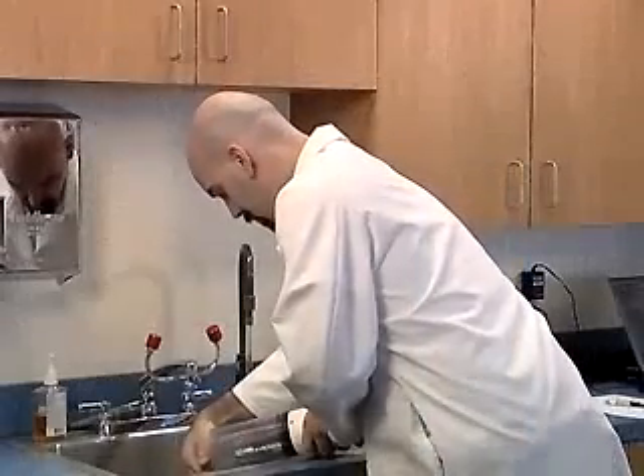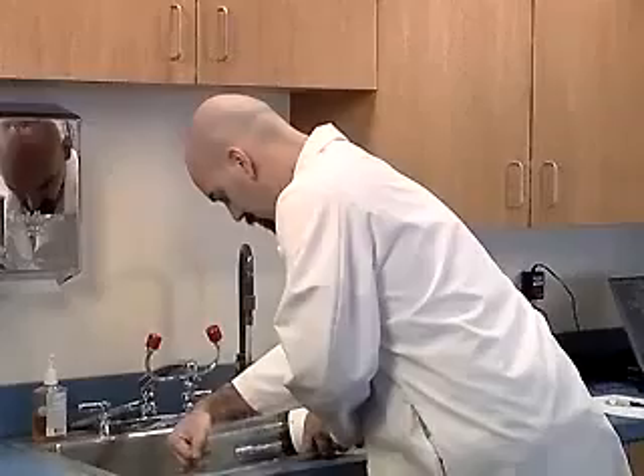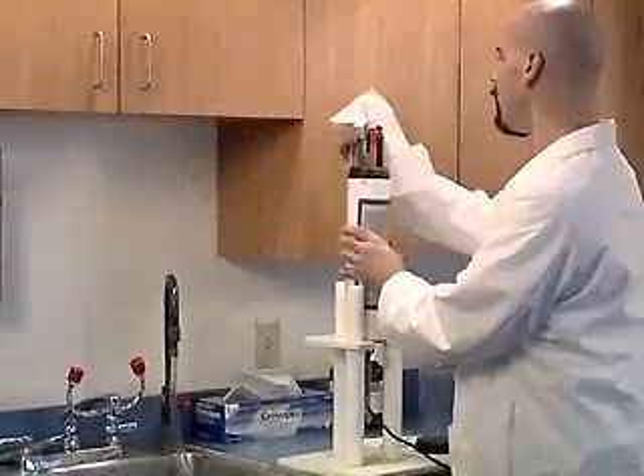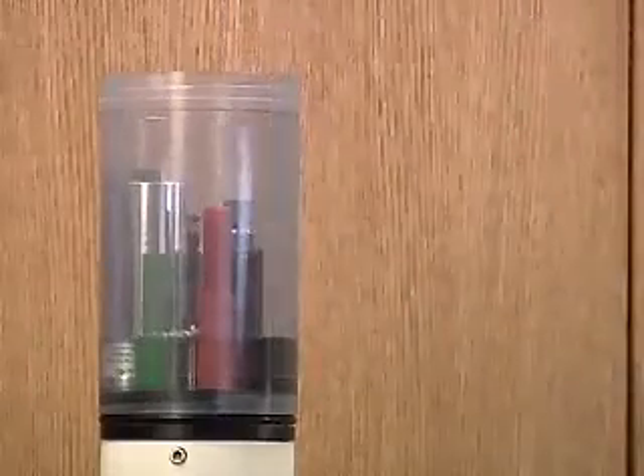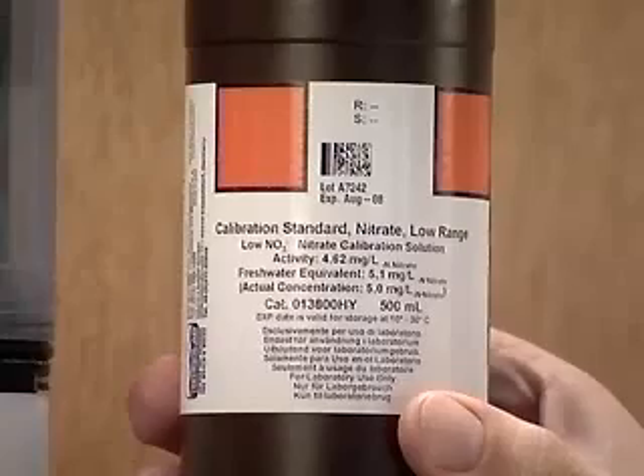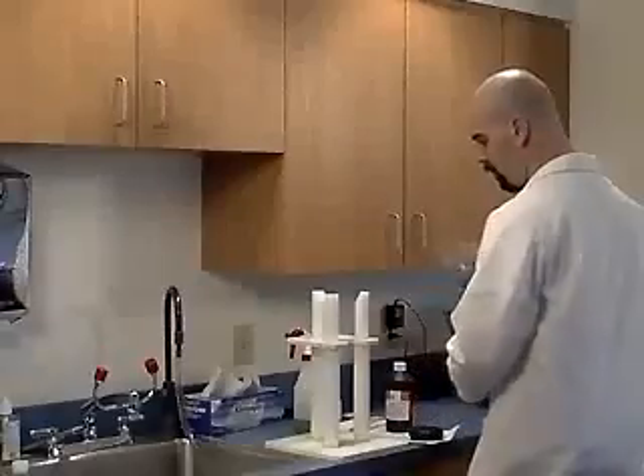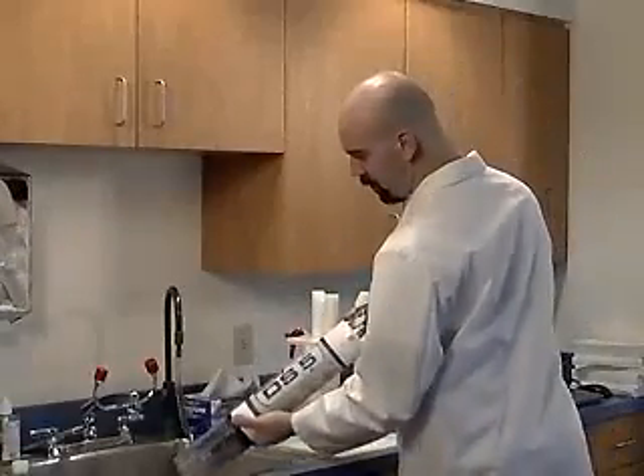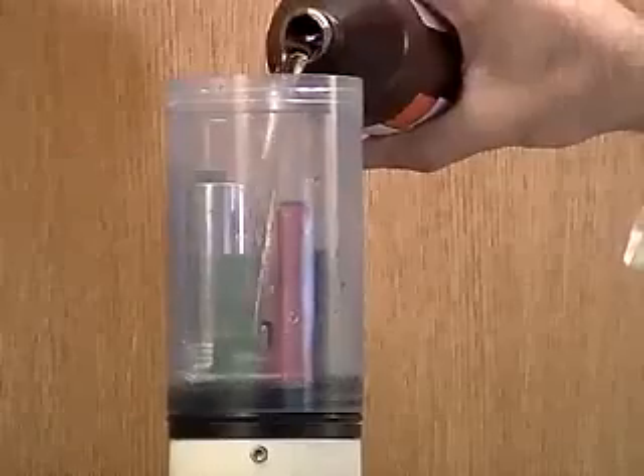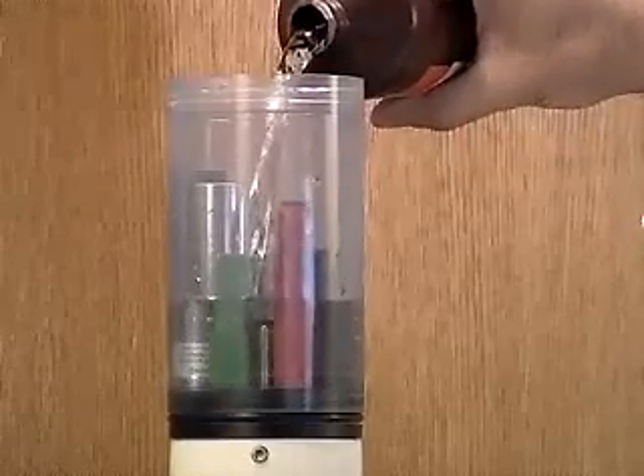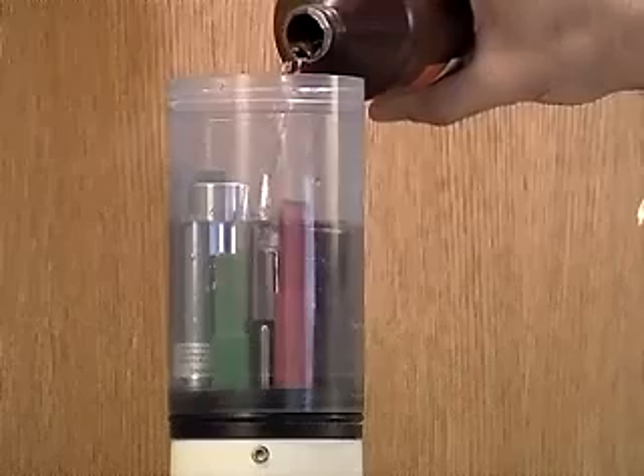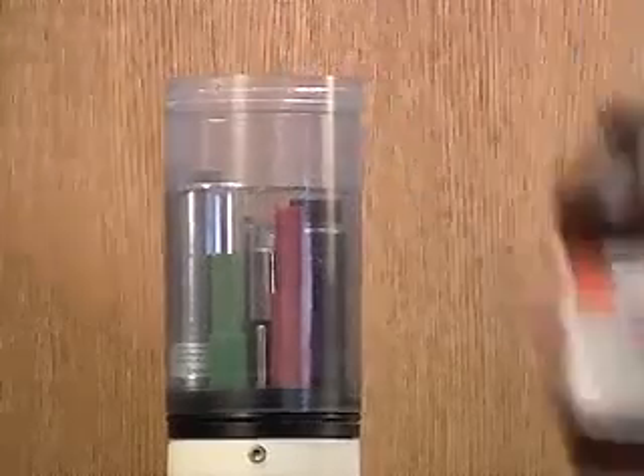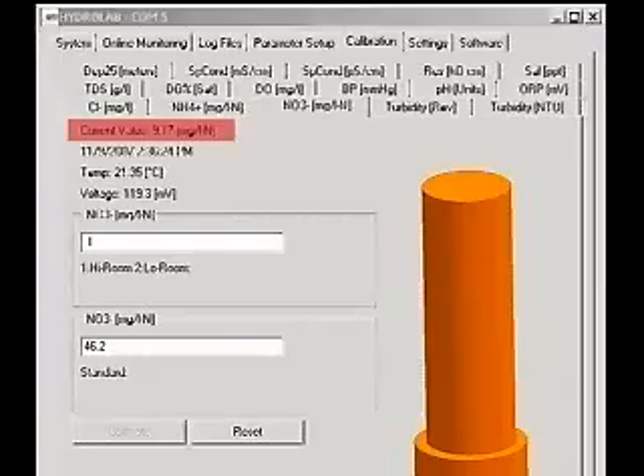Rinse the cup and sensors with deionized water and dry them. Fill the cup about 25% with the room temperature low standard and screw the storage cap on. Shake for 6 seconds. Remove the storage cap and pour the standard out. Fill the cup with room temperature low standard again, this time covering the ion tip and the pH sensor. Wait 5 minutes for the readings to stabilize.